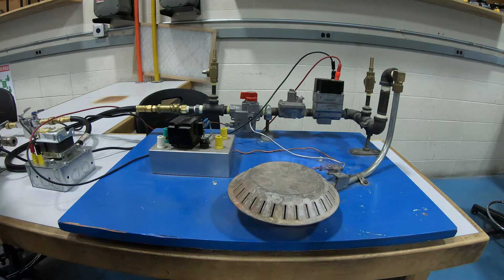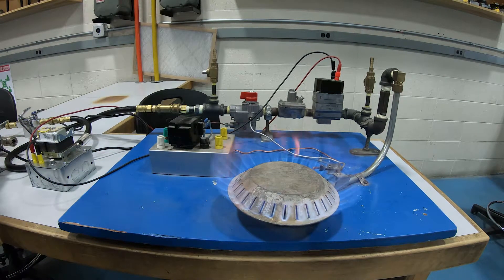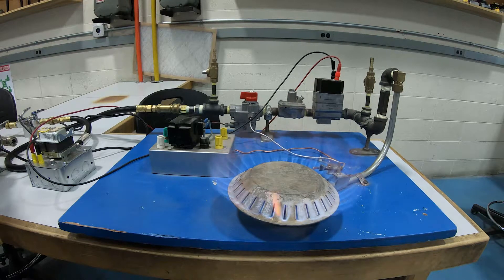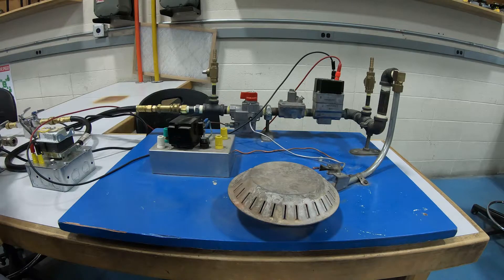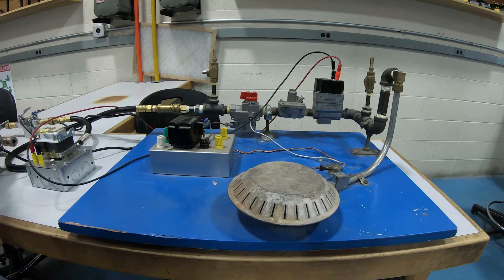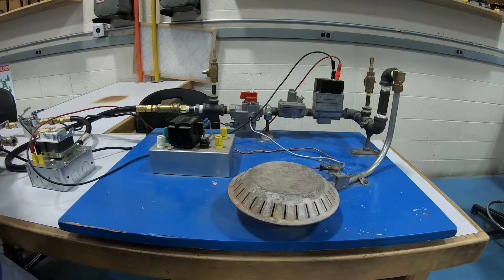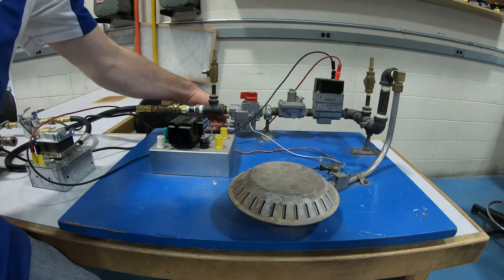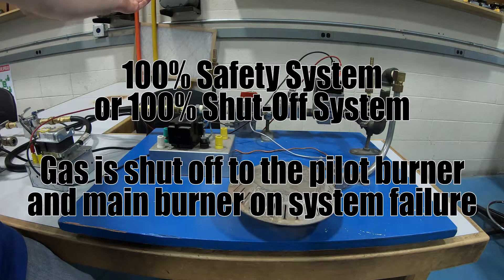If we get a call for heat, the burner starts up. Once the call for heat is satisfied, the burner shuts off. And of course if we have a problem with the pilot light going out, this is what it might look like. I'm going to simulate it. And everything goes out. So we call this 100% safe.